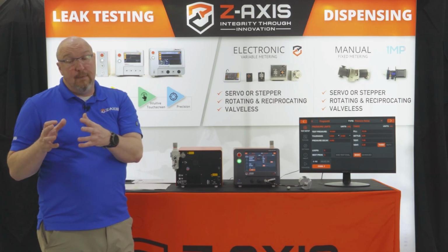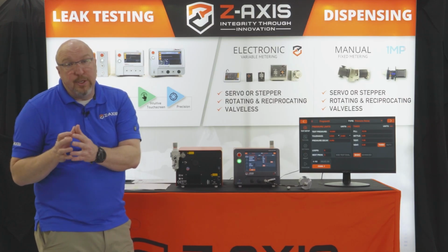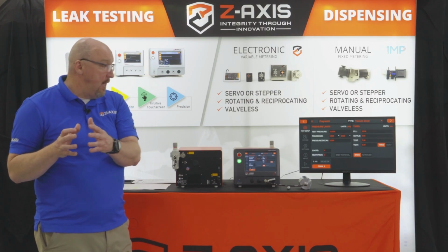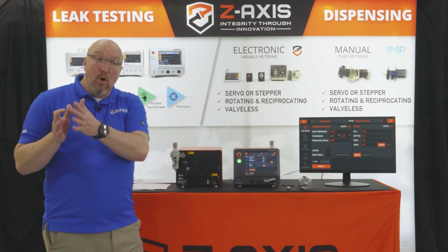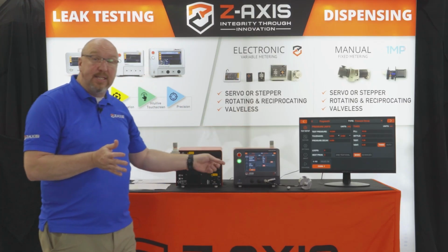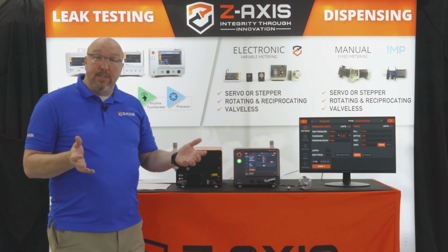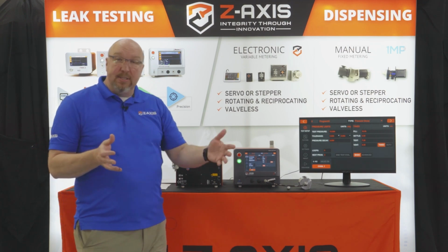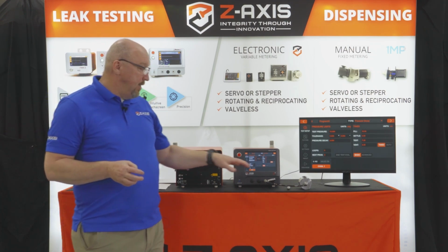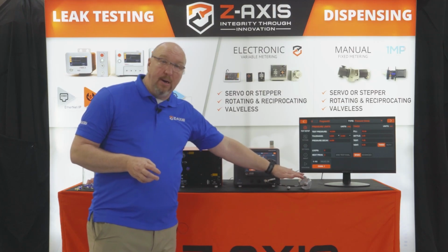It's had time for the part to possibly reduce back in size because it was expanded due to the pressure. And then I can plug the leak standard in and go through 1 through 10 again with the leak standard plugged in and get the results. That way I'm taking a better sampling and I'm getting a more realistic test because I'm not just doing a sampling of 1 like we're doing here.